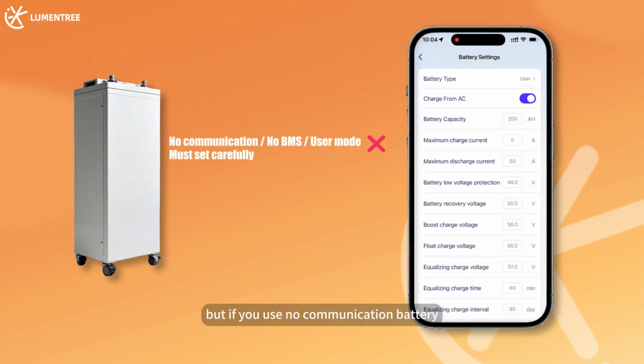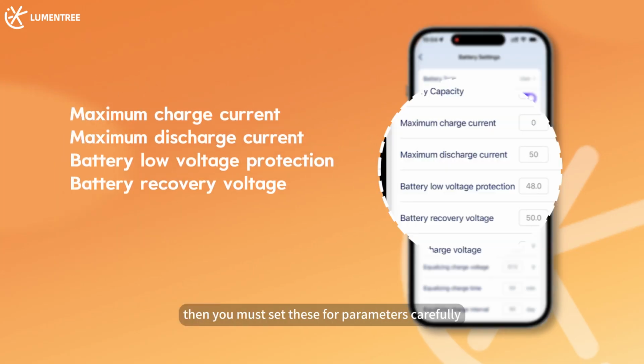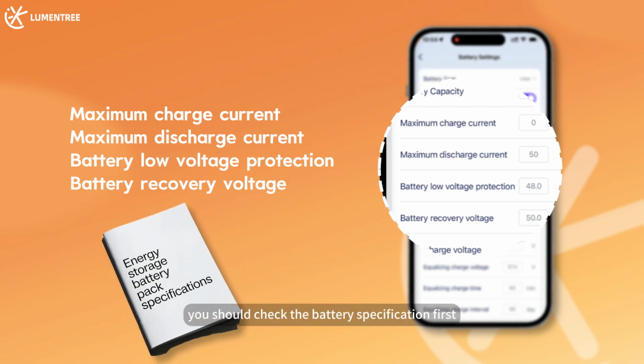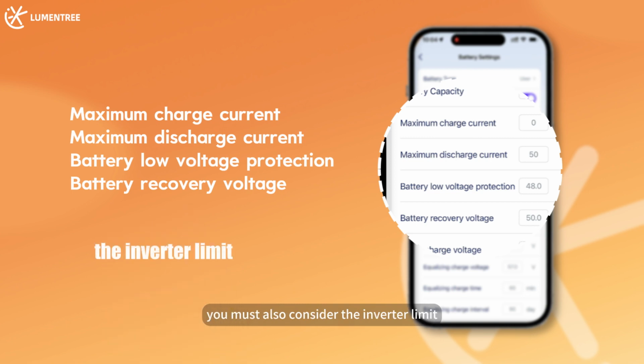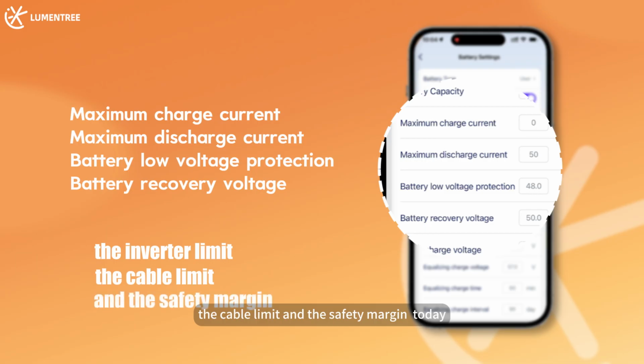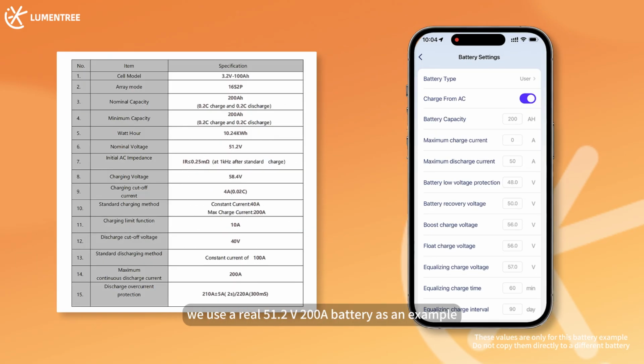But if you use a no communication battery, no BMS battery or user mode, then you must set these four parameters carefully. These four settings should not be guessed. You should check the battery specification first, but do not copy the numbers directly. You must also consider the inverter limit, the cable limit, and the safety margin. Today, we use a real 51.2 volts 200 amperes battery as an example.